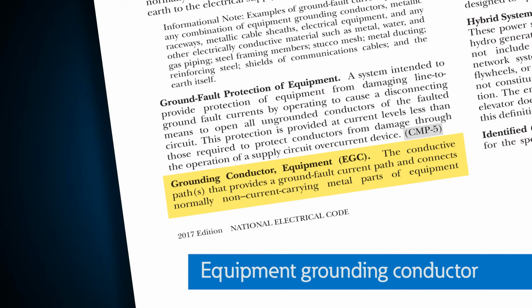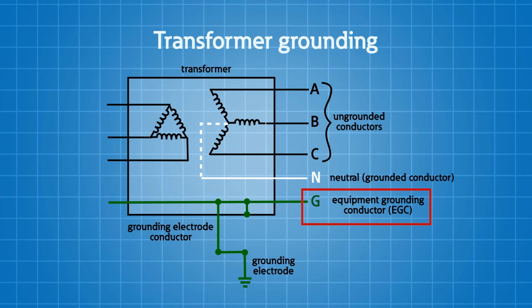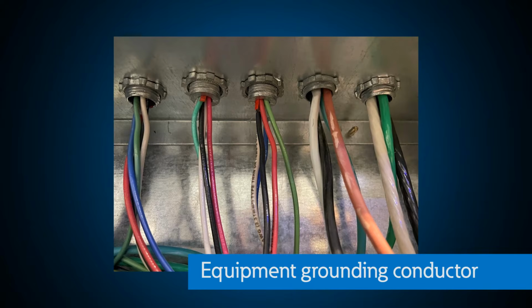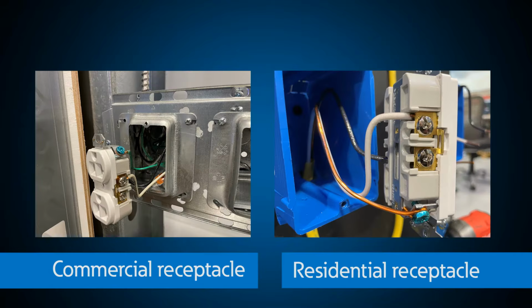Equipment grounding conductor. So we've used that term, let's define it. The equipment grounding conductor is the conductive path that is part of an effective ground fault current path and connects metal parts of the equipment to the system neutral or grounded phase conductor. And that's done back in one location. Think of this as that bare copper conductor that you carry out to all of those loads. Or if you open up any receptacle, you'll see that bare copper conductor that's in the receptacle outlet. That is your equipment grounding conductor. We want that to be a low impedance, and we want that to carry fault current should a ground fault occur in the system.